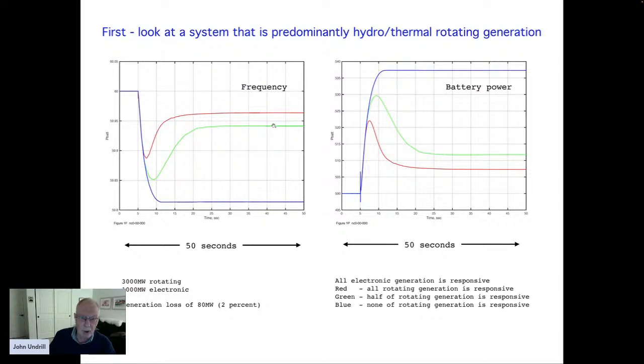Now, once the frequency is stabilized, and this is a minute, this is 50 seconds across, then you can bring it slowly back to 60 hertz or 50 hertz by using secondary control. Secondary control, when I was basically a graduate apprentice, early days, was a young engineer walking along the turbine floor, or the governor floor, grabbing hold of the hand wheel of the red generator and moving its set point up a little bit, walking along 50 feet to the hand wheel of the next generator and moving its speed load reference up a little bit.